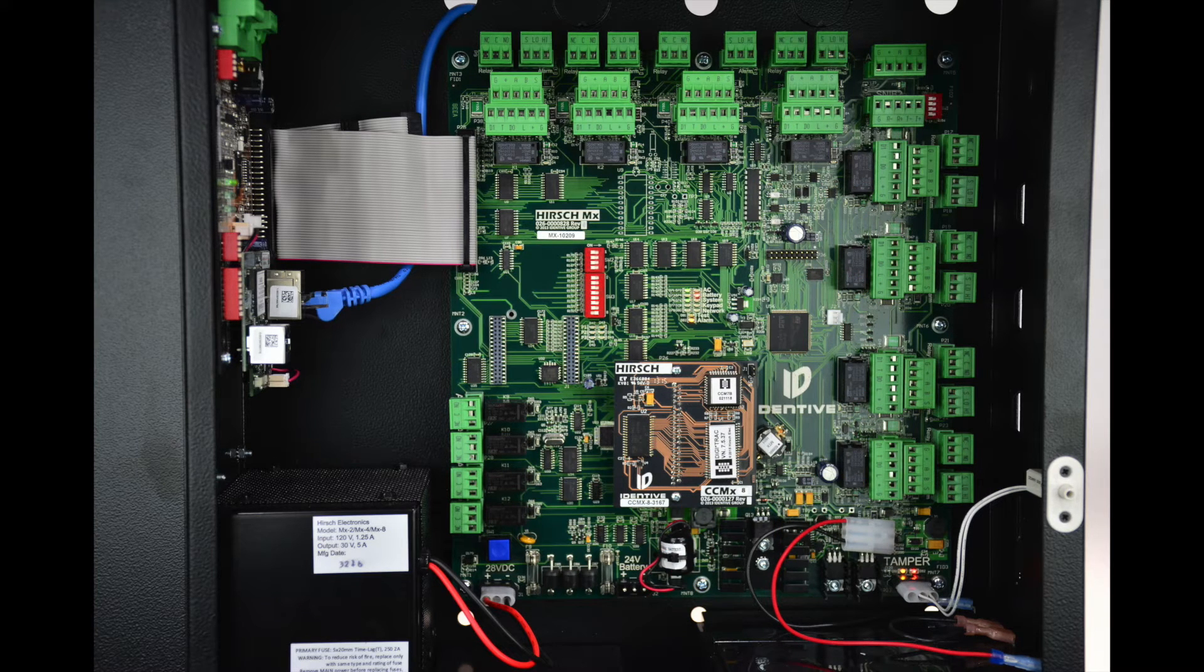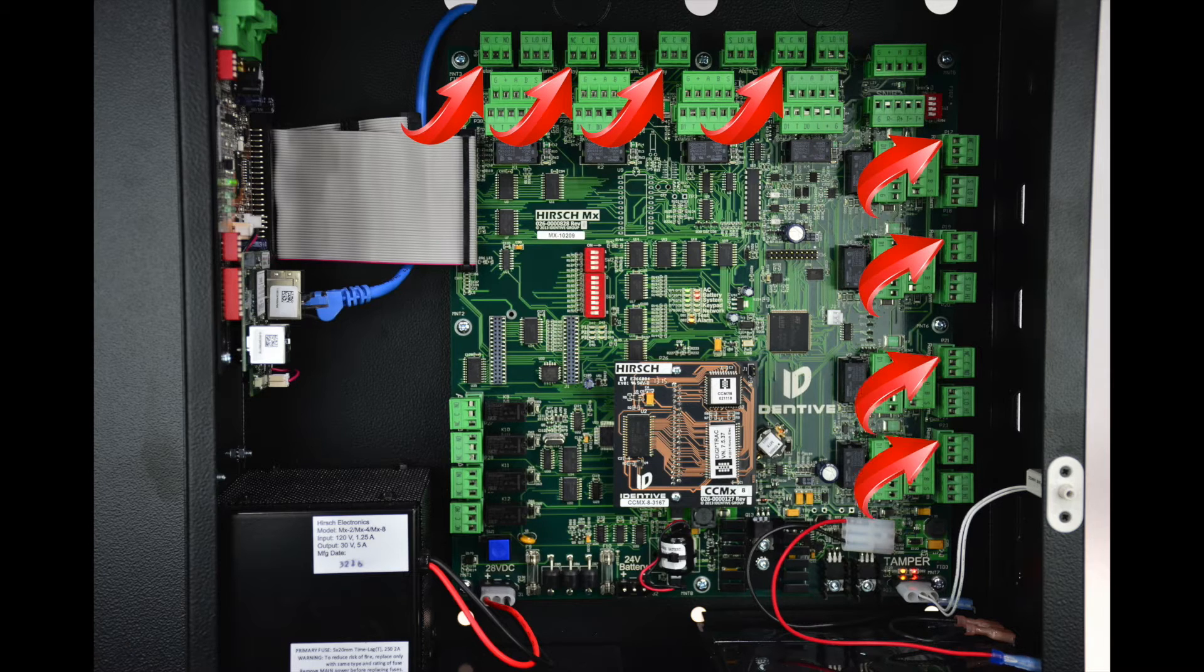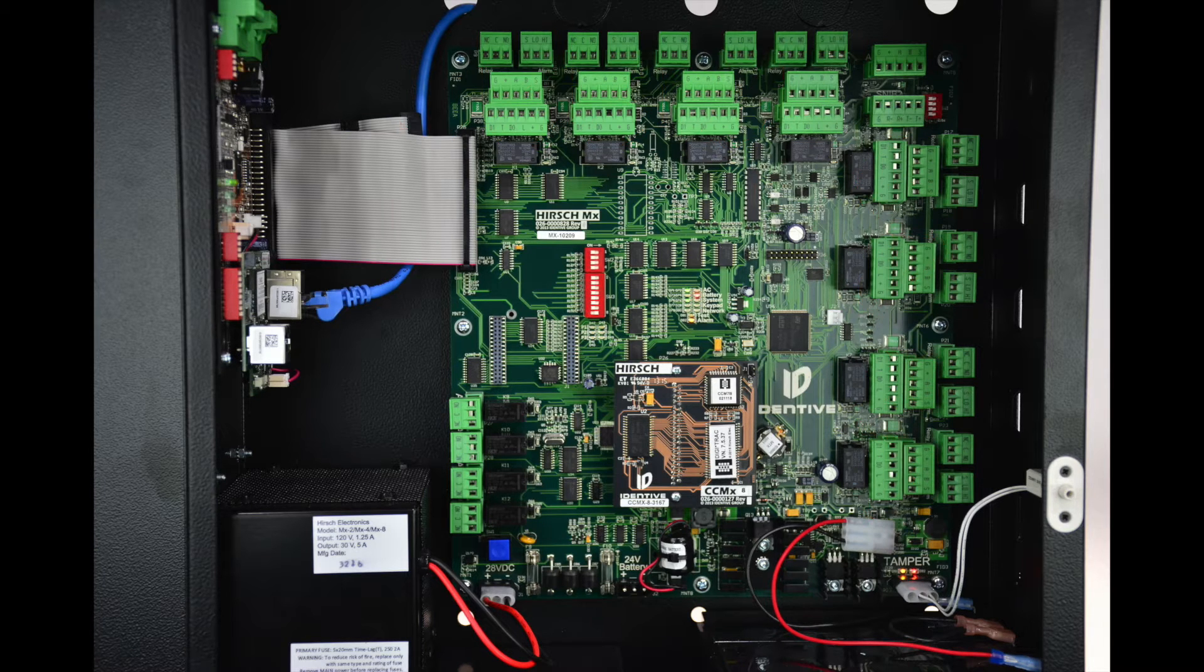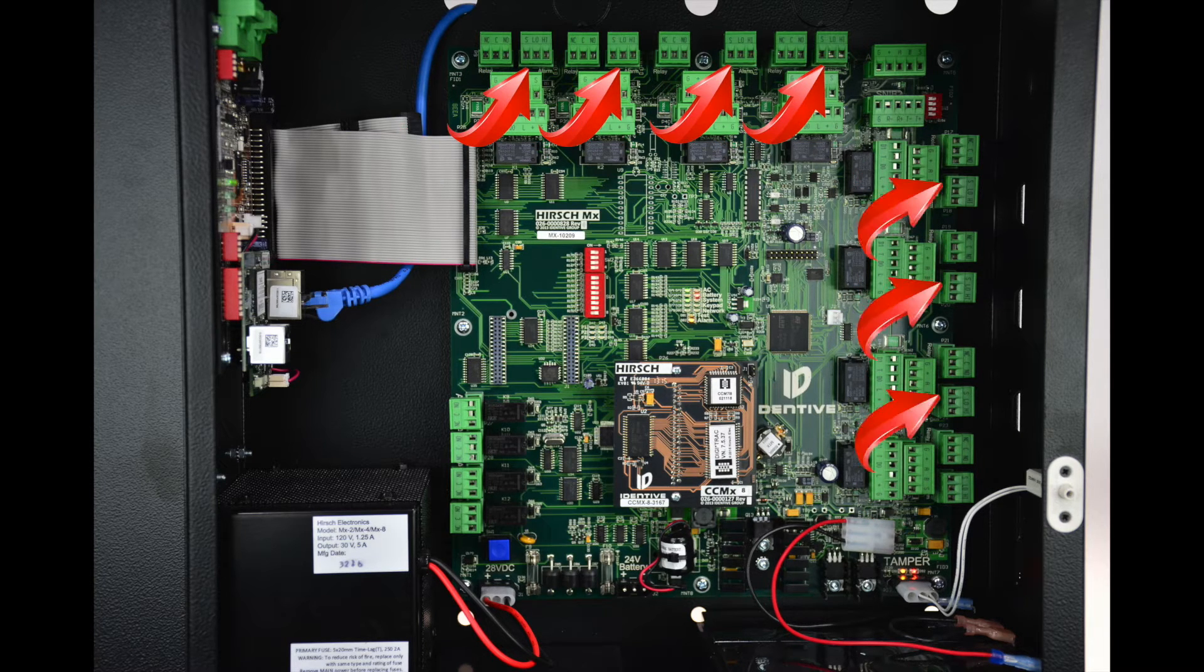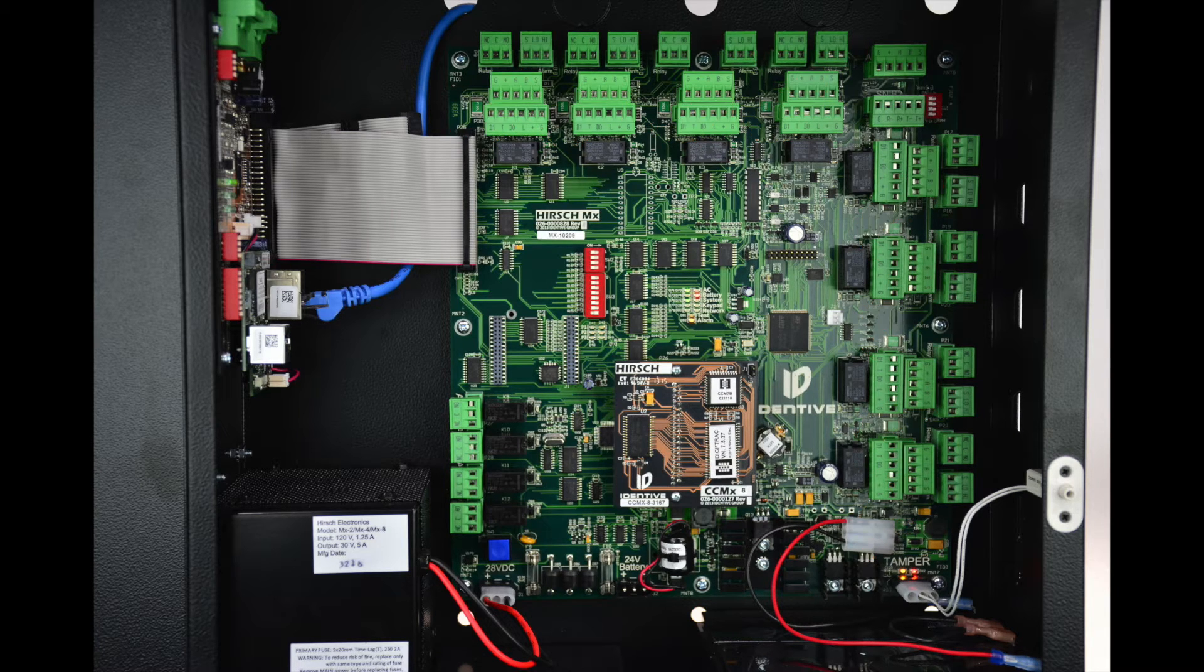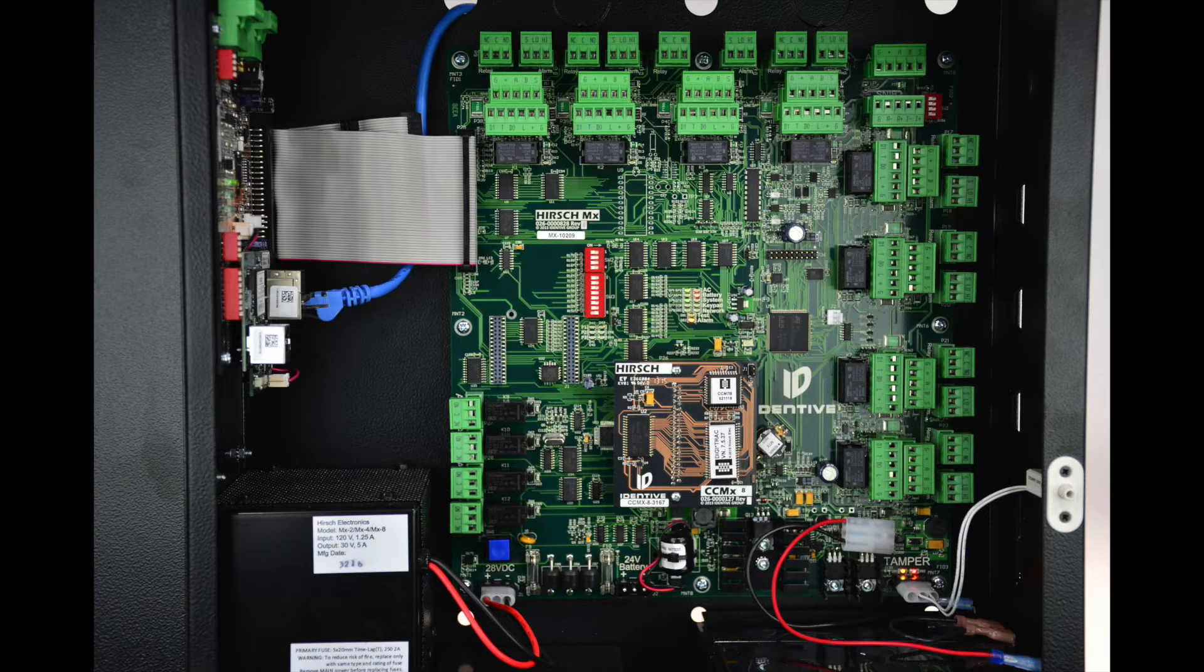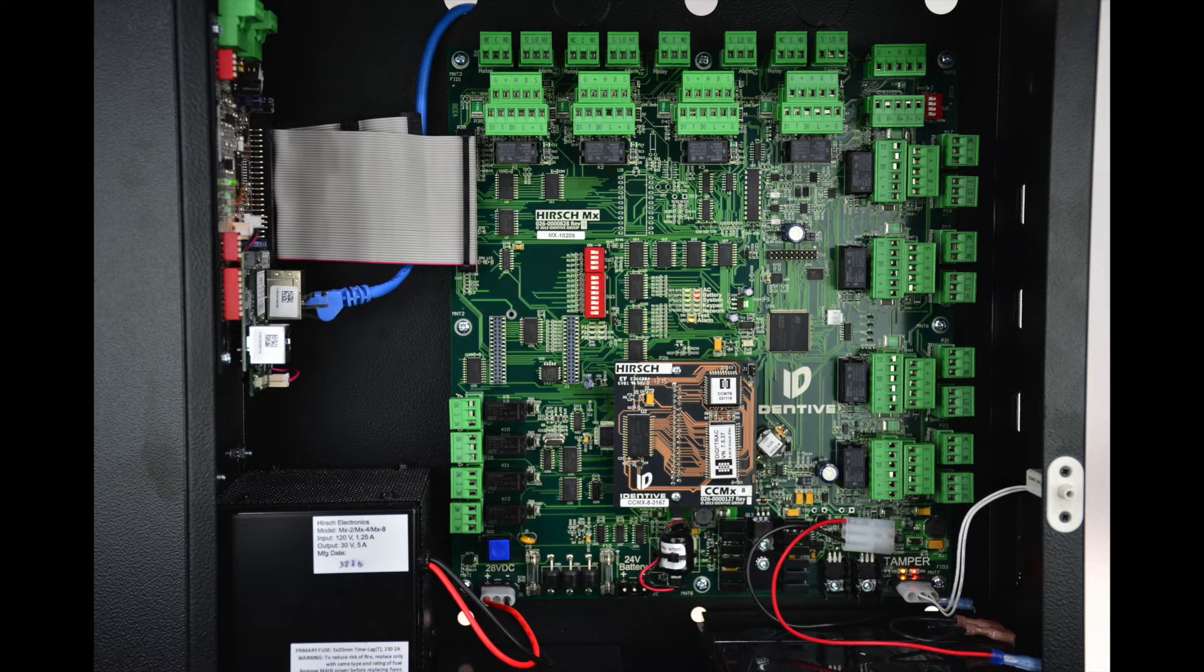Every door has a dry contact output for a lock, such as a strike or a mag lock. Each door also includes a single input, which would connect to one of our resistor packs, such as our MLE-M-3, which would then provide up to three inputs for a door position sensor, request to exit, and tamper. We will go into the MLE-M resistor packs in more detail in a bit.